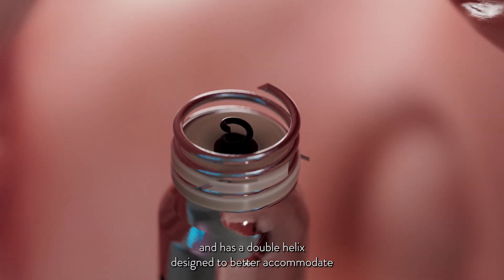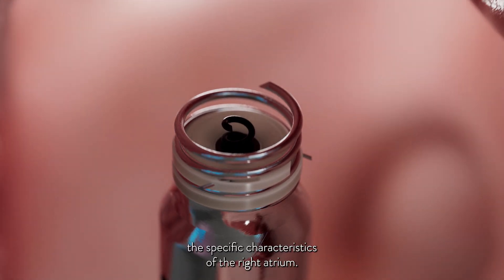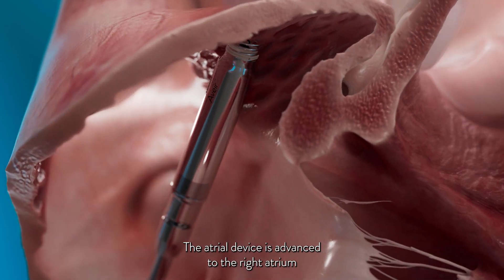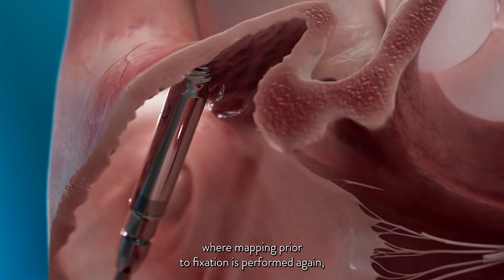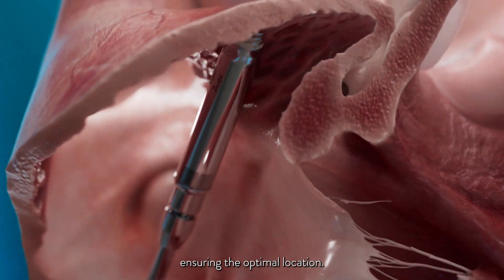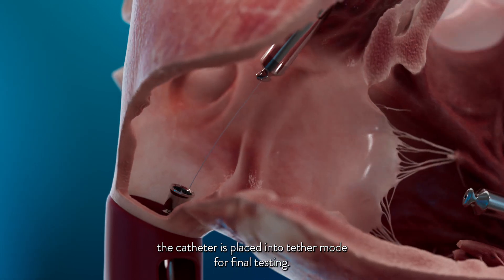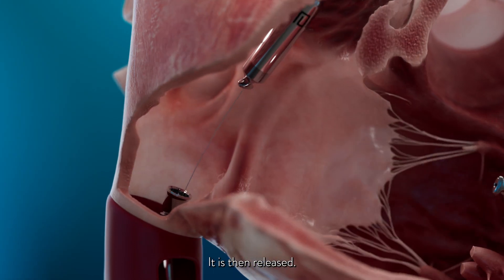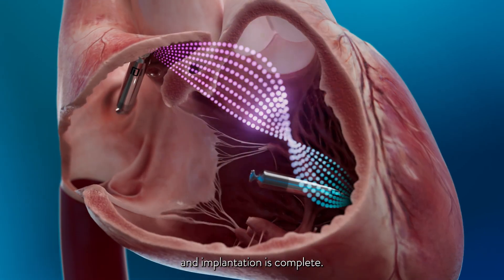The atrial device is smaller and has a double helix designed to better accommodate the specific characteristics of the right atrium. The atrial device is advanced to the right atrium where mapping prior to fixation is performed again, ensuring the optimal location. Once the device is fixated, the catheter is placed into tether mode for final testing, then released. The two devices undergo i2i pairing and implantation is complete.